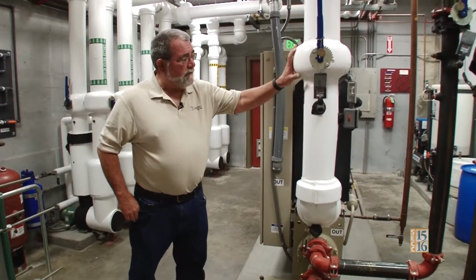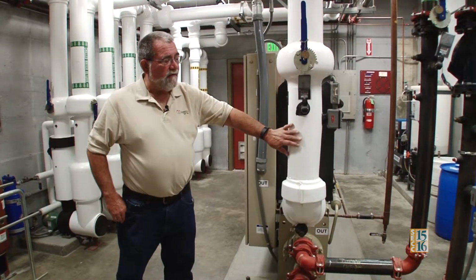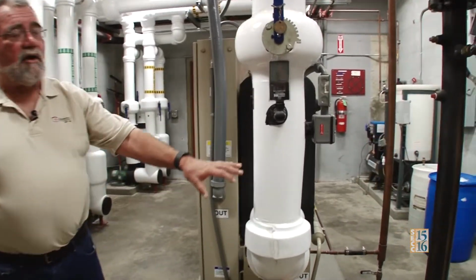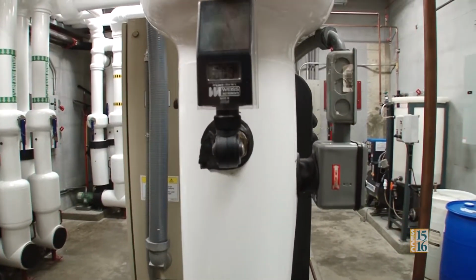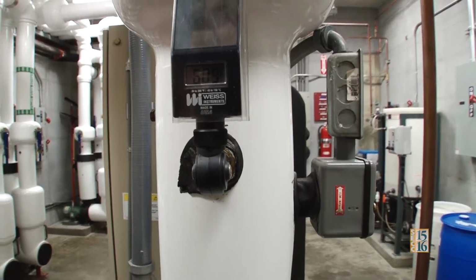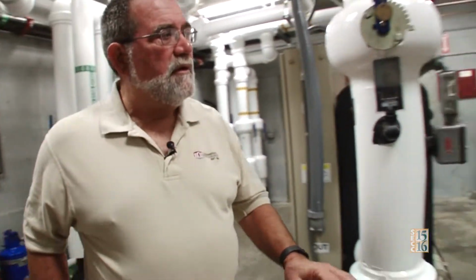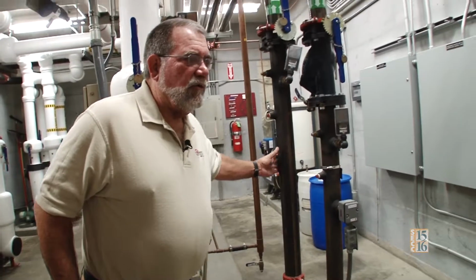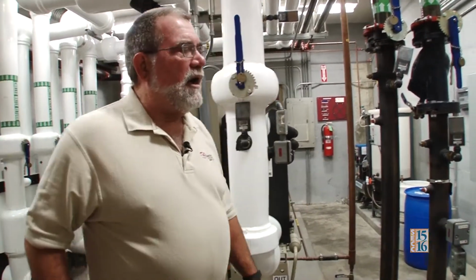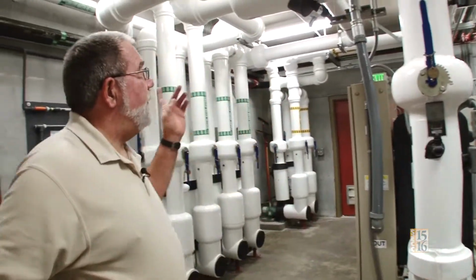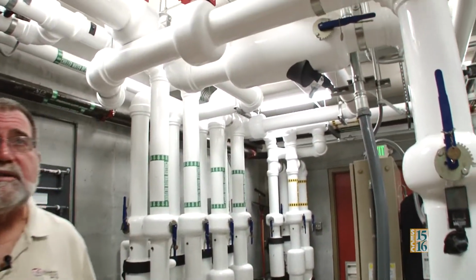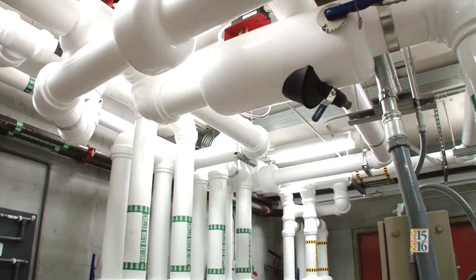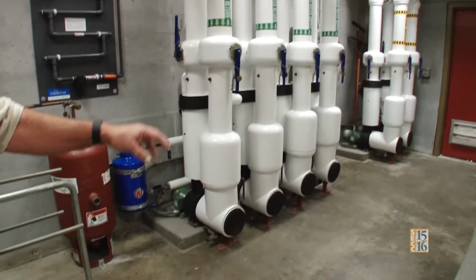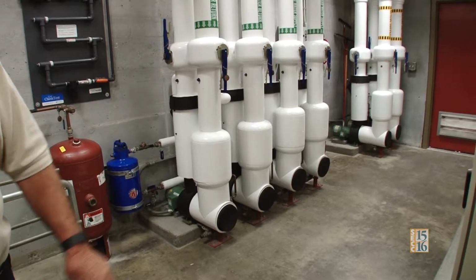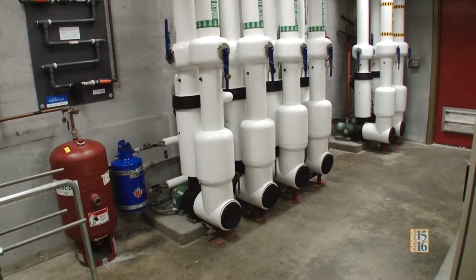We cool water in the pipes covered by white plastic, and that cool water goes out to the air handlers and absorbs heat. We use condensing water to remove heat from the refrigerant, and that goes to the cooling tower. The piping system is a primary-secondary system: the primary pumps run at constant speed, and the secondary loop pumps run off a VFD drive against the far wall.